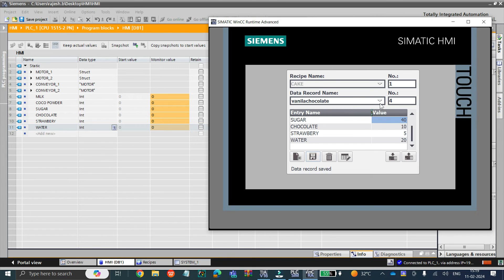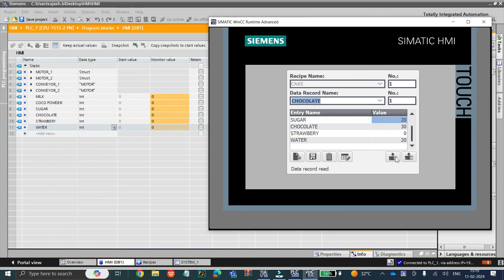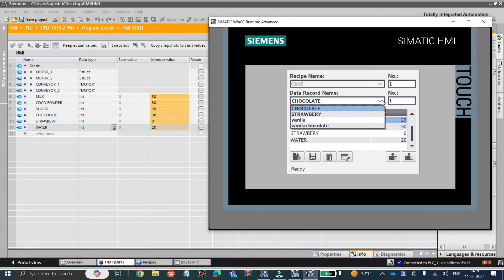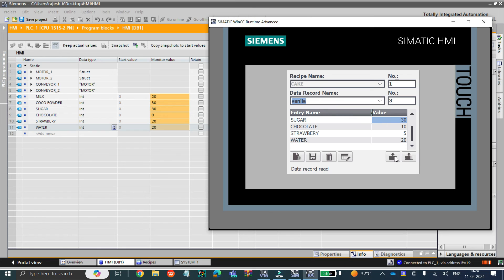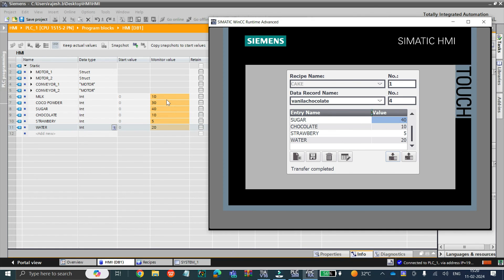Currently we are only playing with the recipes — we haven't downloaded into our project yet. Let's say I want to start production of chocolate cake. I have selected chocolate cake, and this is called the load button. Click on it — you can see the milk is having 30%, cocoa powder 30%, and all the content of the recipe is being executed into your data block directly. You need not have 30 to 40 tags for recipes — only 5 to 6 tags, but the values will be overwritten. Now chocolate production is completed and I want to change to strawberry. I will load it — milk was 30, now it is 20.